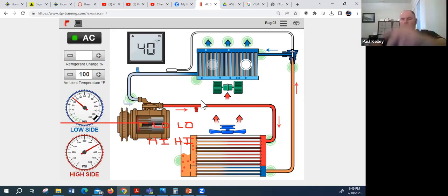And there's one other possibility. There's an overpressure relief device, a PRD, a lot of times on the AC compressor. That can actually release when over-pressurized, and then you'll end up with oil and dye all over the compressor, but you won't find a leak.